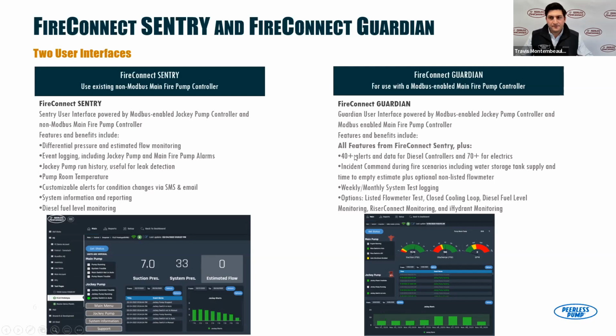One question from Chris Rabondo: can the gateway monitor any pump/controller, or is it specific to Peerless? I know you probably get to this, but great question. Yeah, and we'll address it now. We call FireConnect pump agnostic. Yes, it's a Peerless pump product, but we can monitor any UL/FM fire pump. So it doesn't matter if it's our competition or our own, we'll monitor it. And similarly, we work with the majority of the main UL/FM fire pump controller manufacturers. So Tornatech, Firetrol, Master, and Eaton will connect to any of those via Modbus.